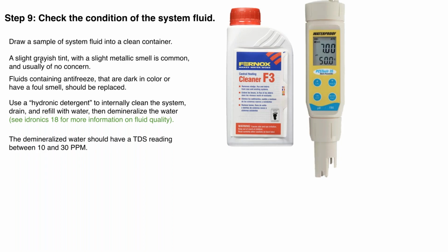You want to demineralize the water. Again, idronics 18 talks about the whole process of that. We're basically taking the calcium and magnesium salts out of the water. We're reducing its conductivity, and a simple, inexpensive meter like this, you can test looking for between 10 and 30 parts per million total dissolved solids. That is basically removing these salts from the water, and the chemistry of a demineralized water and antifreeze is excellent. Very hard water and antifreeze, that's not the best chemistry. So demineralizing the water is, I feel, an important step in commissioning any hydronic system today.